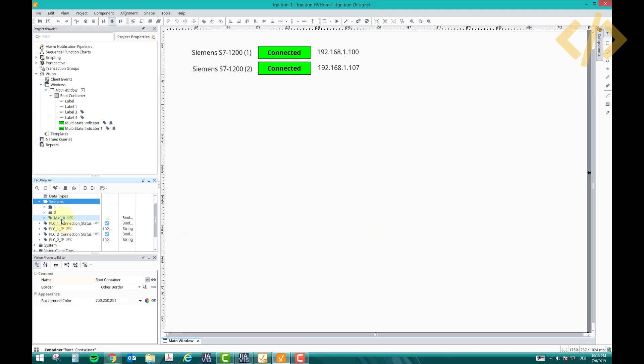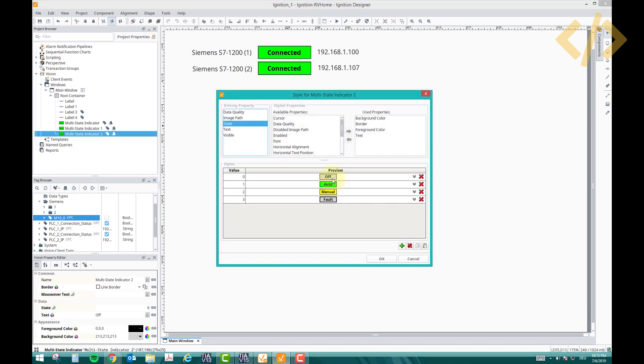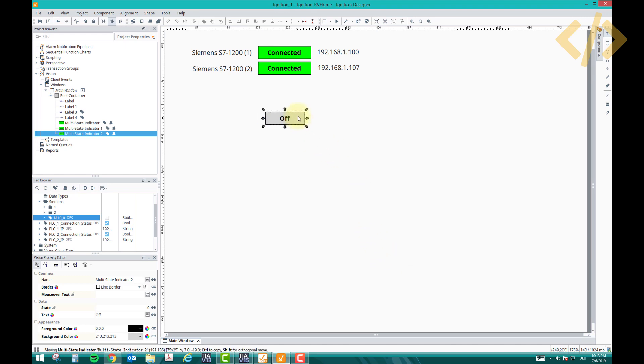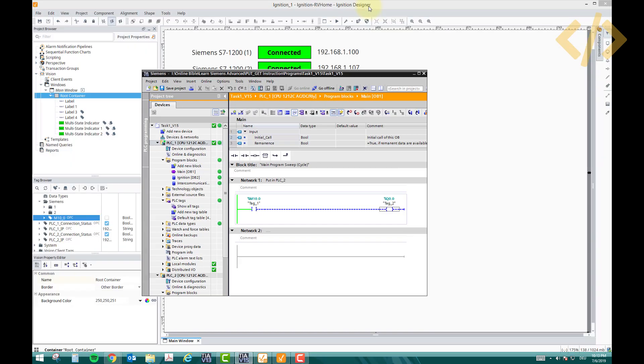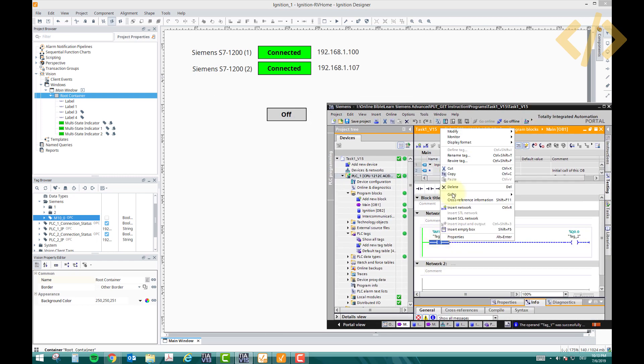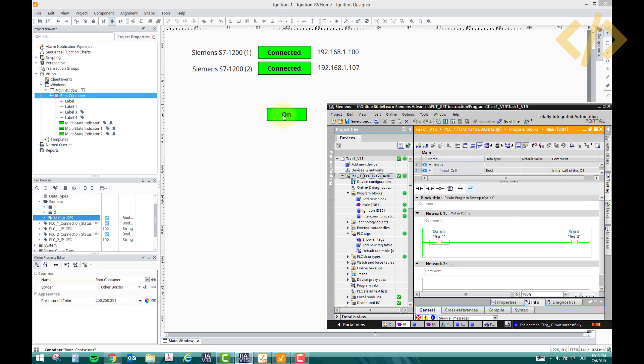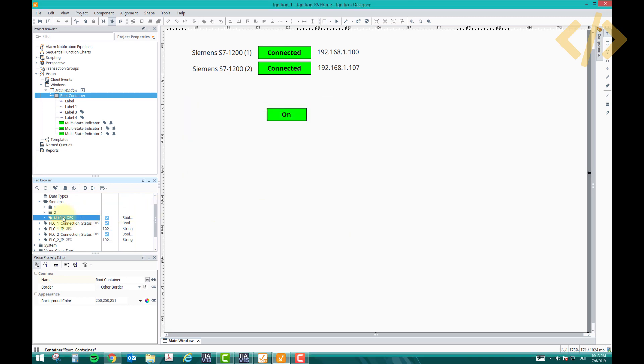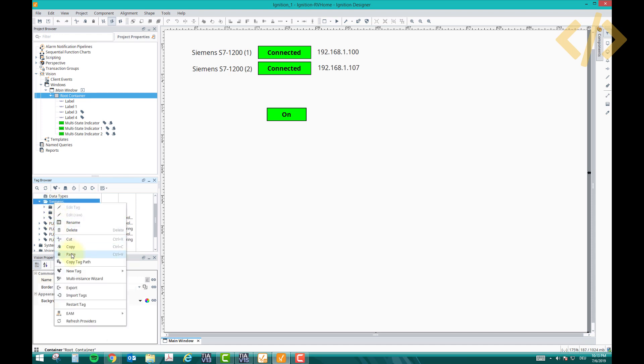Take this tag and add a multi-state indicator. Set it so when it's off it shows one state, and when it's on the text changes to 'On' and the color becomes green. Let's test this in TIA Portal — I'll energize M10.0 manually. You can see it's now on in both the PLC and the SCADA screen, confirming it's reading M10.0 correctly.